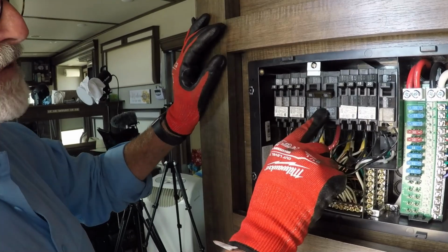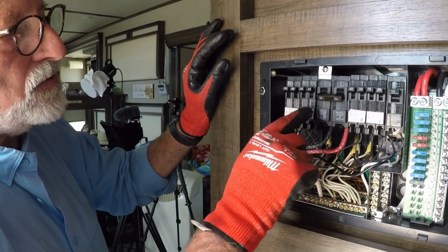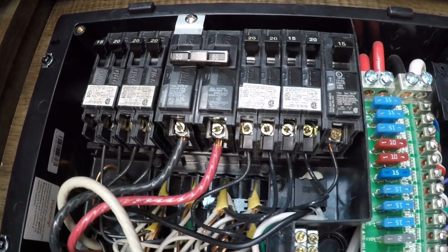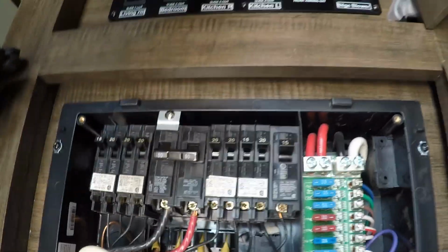Okay, so the 50 amp is in. Now we're going to do the 220s, and that's this one. That was the other one that was warm. And there's two more wires down here. These are smaller wires similar to these because they're only 20 amps, and these are 50 amps. They've got the big wire coming into it. So now we'll loosen those up.